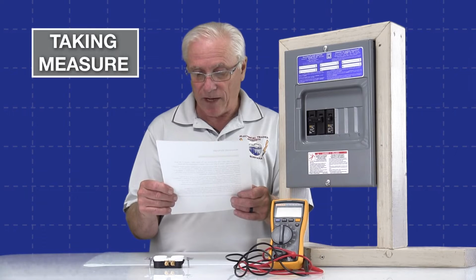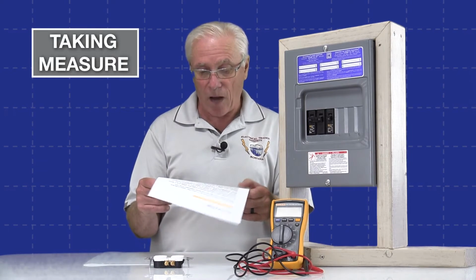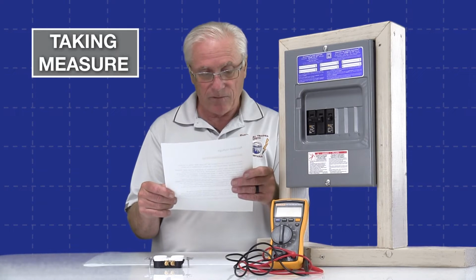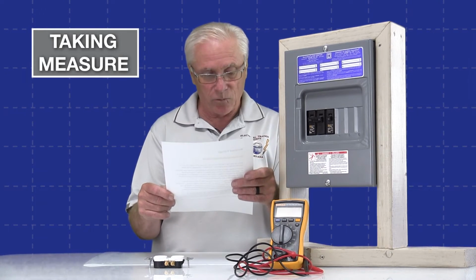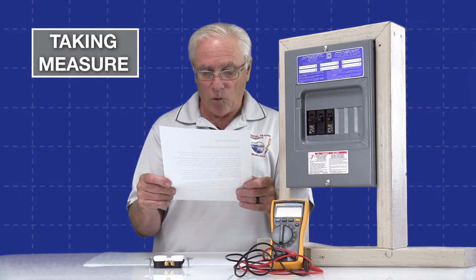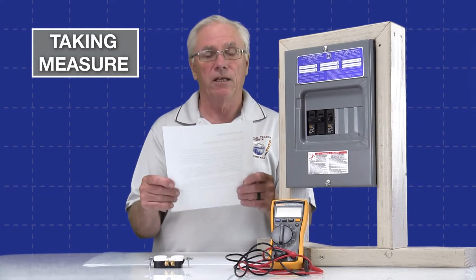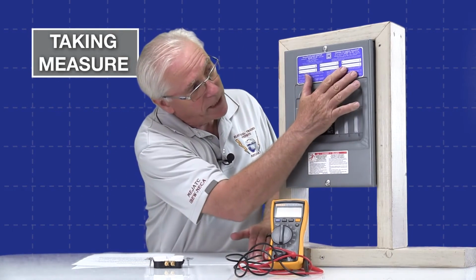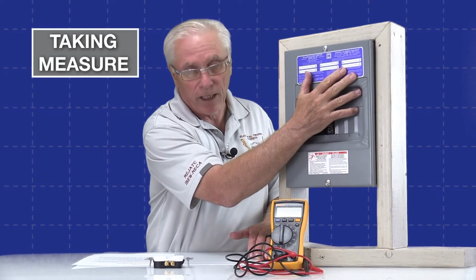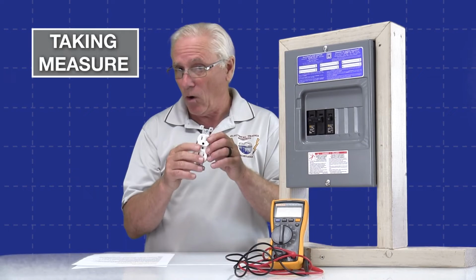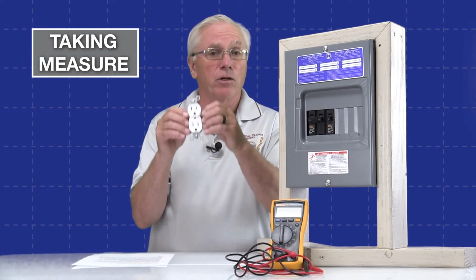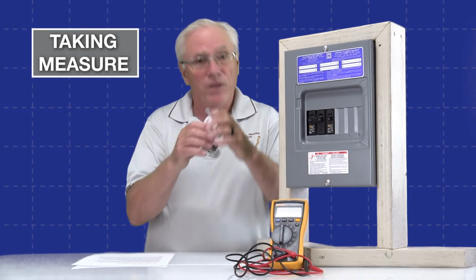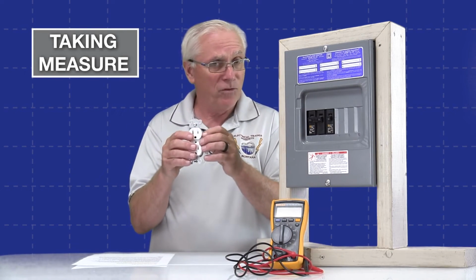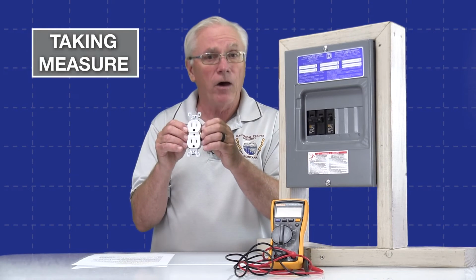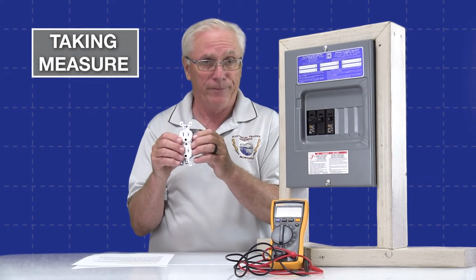This means that the electrical devices designed for use in such systems are built to operate optimally within the specified voltage range. In oversimple terms, it is the voltage of design for a system and any associated devices. And it is a range, and just to give you a perfect example of that, if you were able to read this, this is rated for 120/240. On the 120 side, the devices in your home, like this receptacle, are actually rated for 125 volts. This is 120. So there is a range that it operates in. Sometimes we may actually see the true rated value on our meters, but typically it's somewhere above or below that.